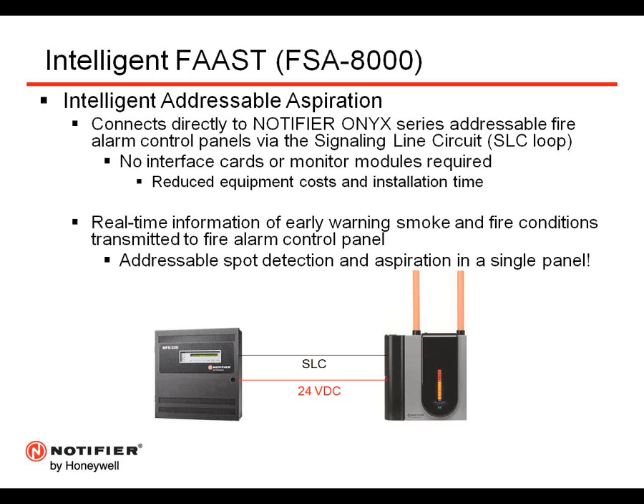So it's intelligent aspiration that's going to now allow us to directly connect this to our Notifier ONYX series addressable fire alarm control panels via the SLC loop or the signaling line circuit loop. What does this mean as we compare this to maybe some other technologies or other alternatives for aspiration with Notifier? Well, it's going to reduce equipment costs and installation time, because there's no interface cards or monitor modules that are required to purchase, install, configure, and wire. It's going to provide robust, real-time information, early warning smoke and fire conditions transmitted directly to the fire panel over the SLC loop. It's going to enable us to combine addressable spot smoke detection and addressable aspiration smoke detection in a single panel.